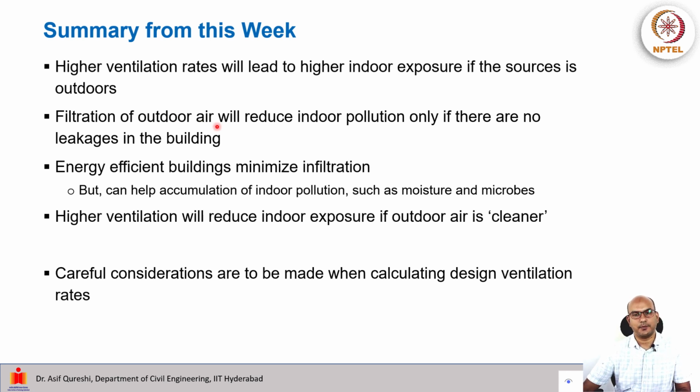Filtration will help. It will reduce indoor pollution, but only if there are no leakages in the building, because as we have seen, leakages tremendously reduce the efficiency of filtration towards reducing the health burden. Energy efficient buildings will generally minimize infiltration, but since we are minimizing the infiltration, these buildings can help in the accumulation of indoor pollution such as moisture and microbes.